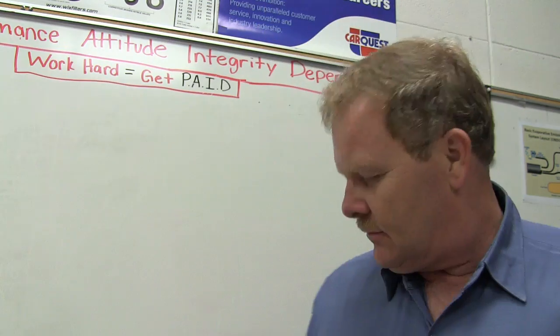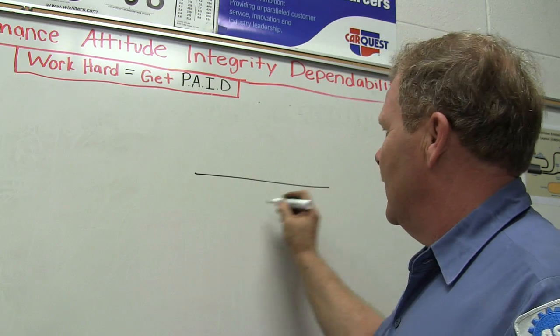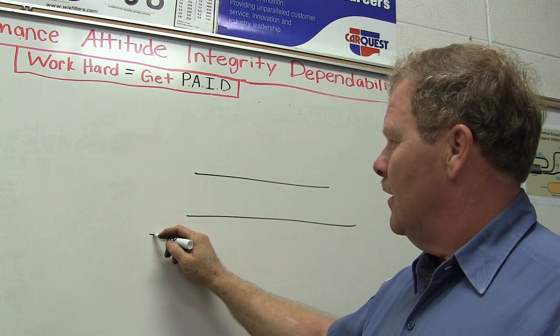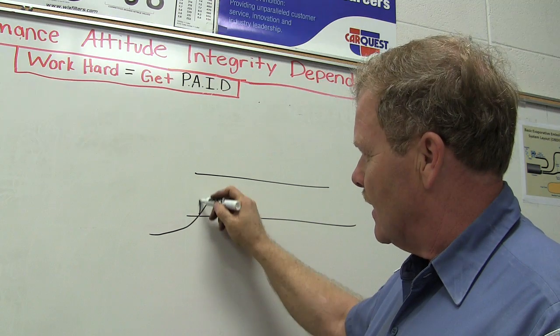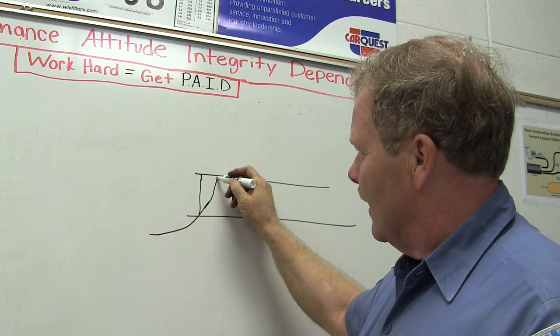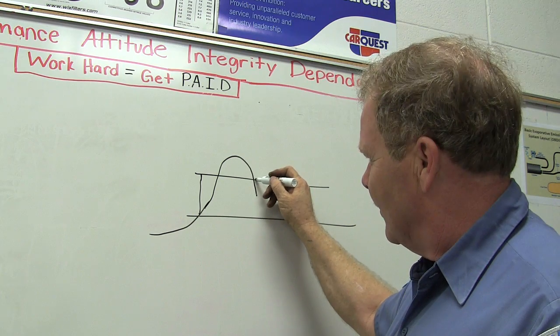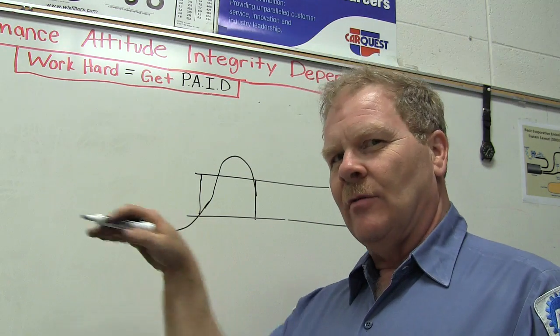So anyway, that's input conditioning. This is what the computer does. It has a threshold setting. When this analog signal breaks over that threshold, it translates that to an on. It keeps it on until it breaks over going back the other way, and then it translates it to an off. See what I'm saying? So it actually conditions those inputs so they'll be digital.